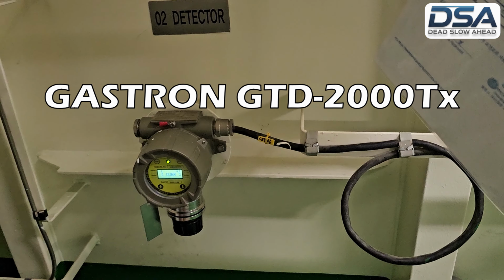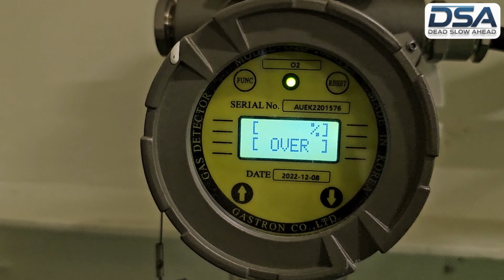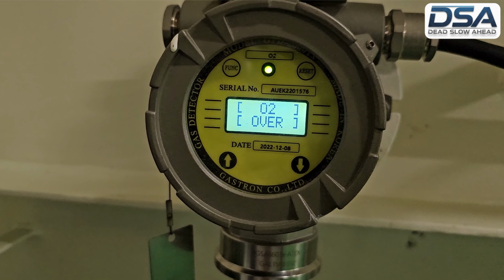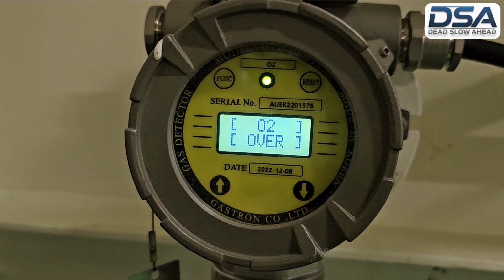As you can see, this is the GASTRON GTD 2000 TX oxygen gas detector, and right now it is showing an over condition which clearly indicates something is abnormal in the system. Before jumping to the conclusion that the life of the sensor is over, we first did a normal check: we performed zero calibration and span calibration, but unfortunately both were failed attempts. Then we went a little deeper into the troubleshooting.